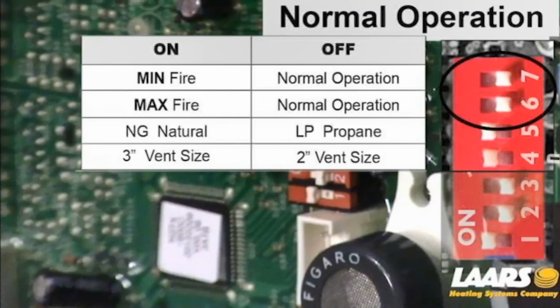You leave the job, and I guarantee you, if it's a cold day, within 24 hours you're going to get a phone call that the boiler's running and they don't have enough heat in the space or the house. So make sure those dip switches are back in the off position when you're done. Lastly, you're going to reinstall your outdoor sensor. And if you made any adjustments, such as raising a set point to keep the boiler running long enough or longer for high fire operation, go back and readjust your settings.